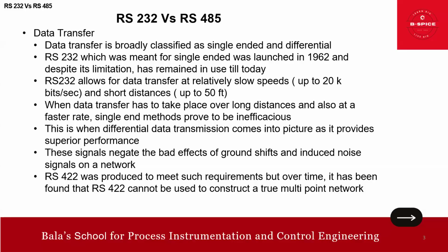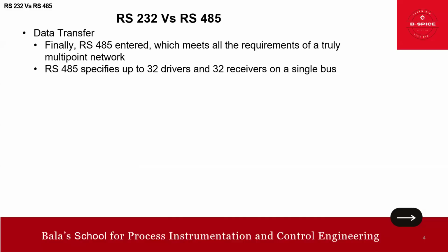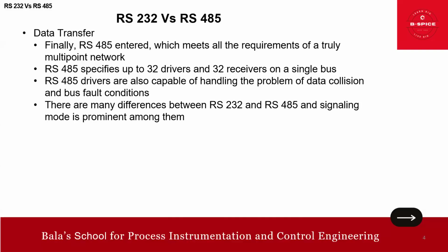So, to answer all this, finally RS-485 entered, which meets all the requirements of a truly multi-point network. RS-485 specifies up to 32 drivers and 32 receivers on a single bus. Just imagine the advantage. RS-485 drivers are also capable of handling the problem of data collision and bus fault conditions.